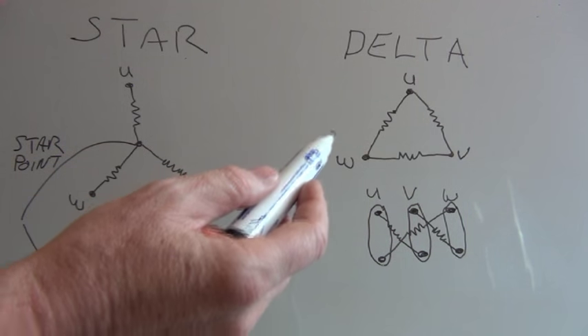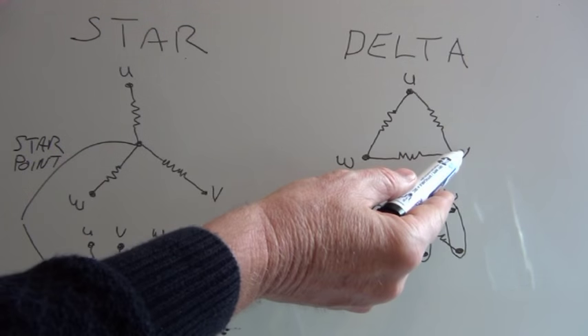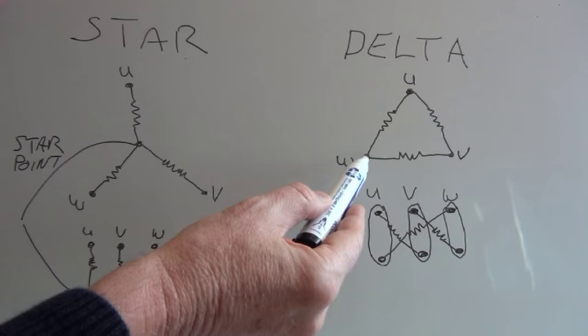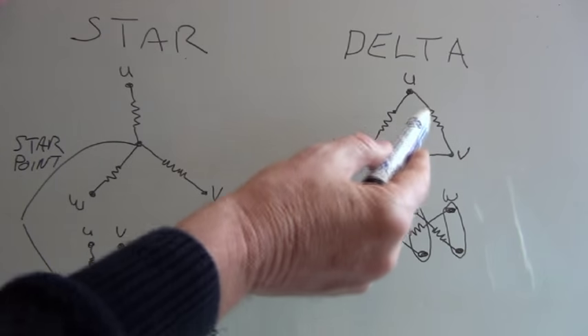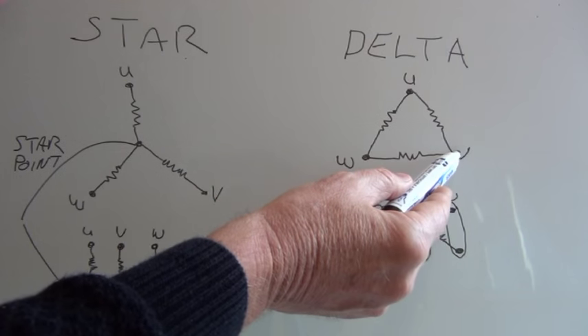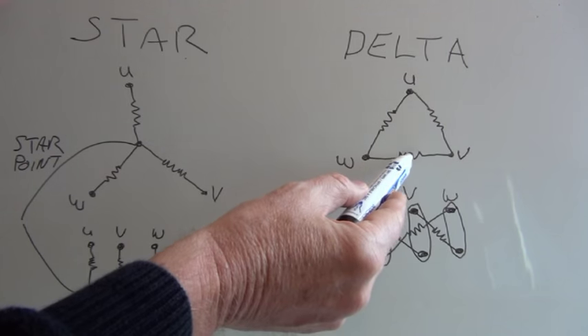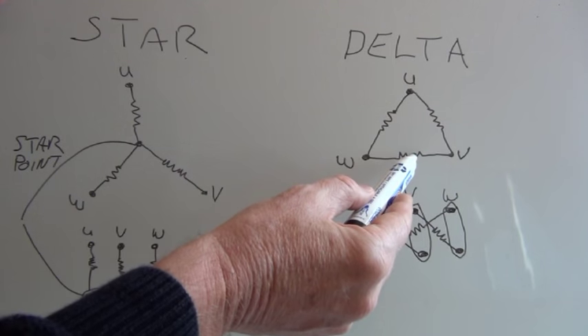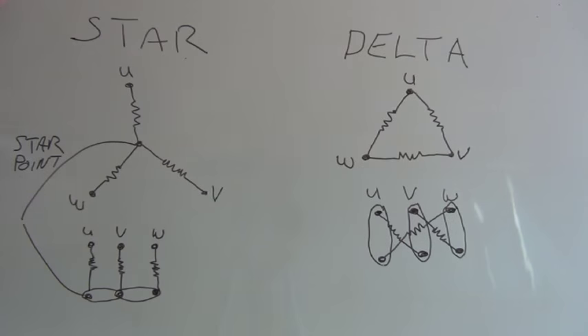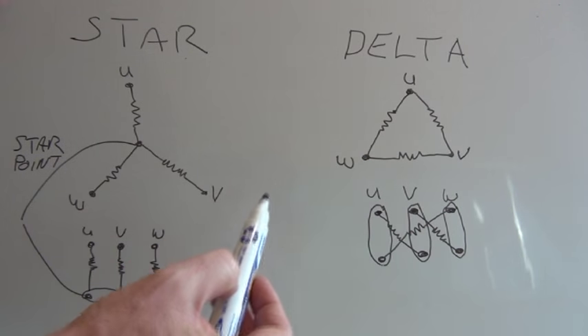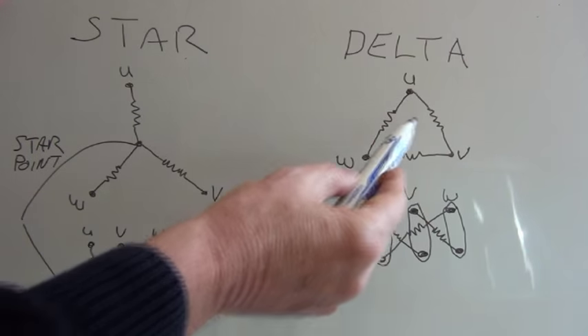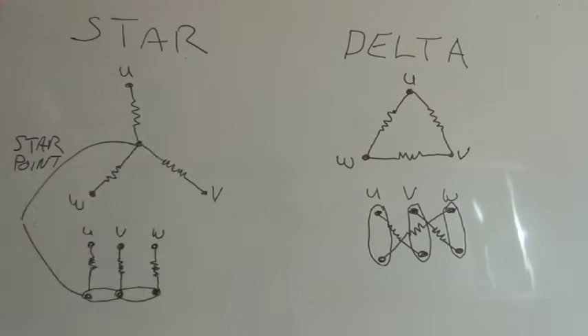If we're doing the test on the delta configuration, we can check between U and V, V and W, and then U and W. But bear in mind that this configuration is different to the star configuration. If we are checking between U and V, then we've also got this and this resistance connected in series but also connected in parallel with that. You would get the same reading across U and V, V and W, and U and W, but if you wanted to calculate it, you would have to use a series and a parallel circuit calculation.